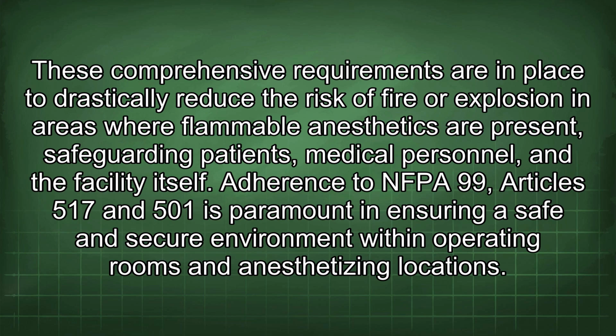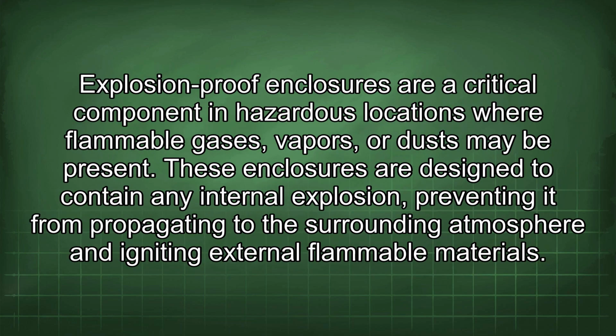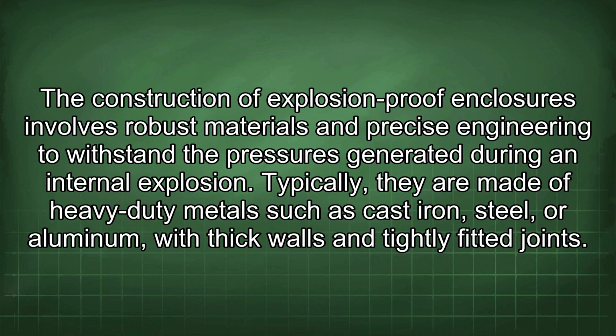Explosion-proof enclosures are a critical component in hazardous locations where flammable gases, vapors, or dust may be present. These enclosures are designed to contain any internal explosion, preventing it from propagating to the surrounding atmosphere and igniting external flammable materials. The construction of explosion-proof enclosures involves robust materials and precise engineering to withstand the pressures generated during an internal explosion.